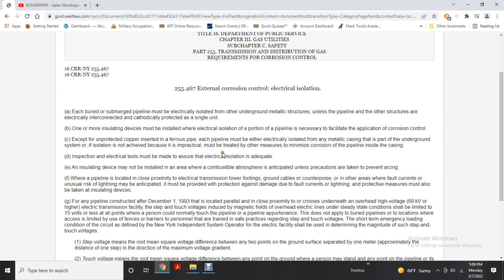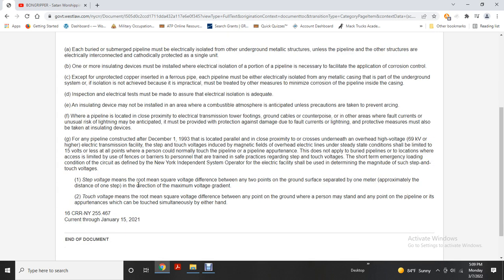Inspection and electrical tests must be made to ensure that electrical insulation is adequate. Precautions are required where pipelines are located in close proximity to electrical transmission line tower footings or in areas with unusual risk of lightning. Protection against damage due to stray currents and lightning must be provided. These measures must also be taken on insulating devices for any pipeline constructed after December 1, 1993, located parallel to or crossing underneath overhead high voltage lines at 69 kilovolts or higher.